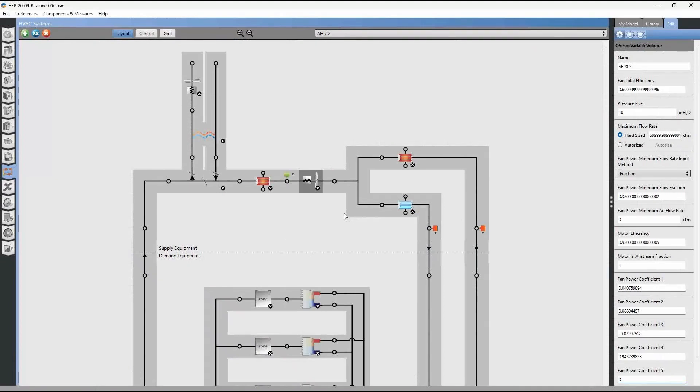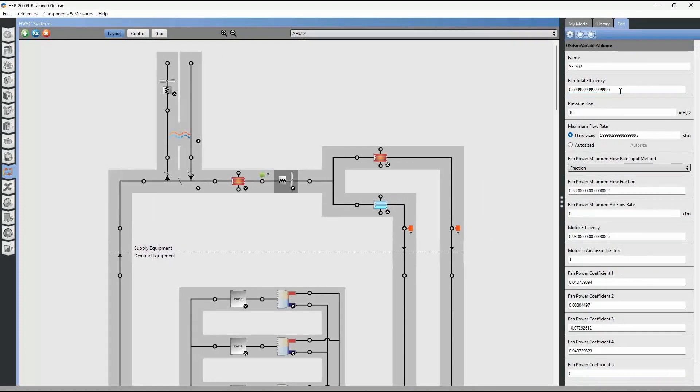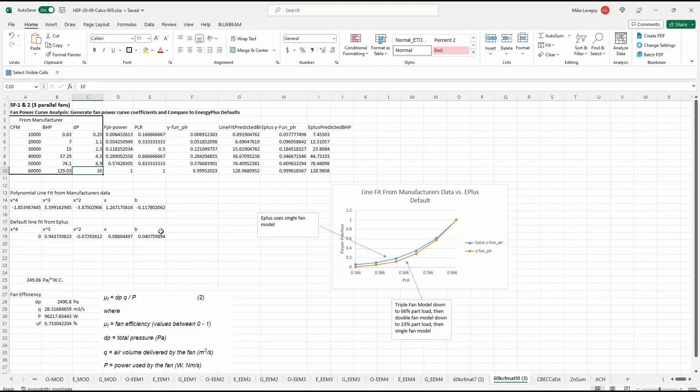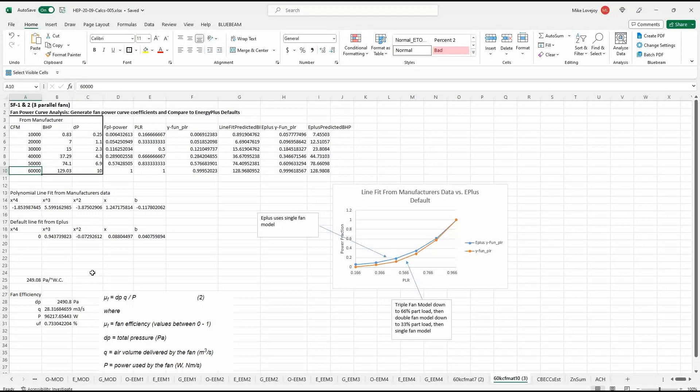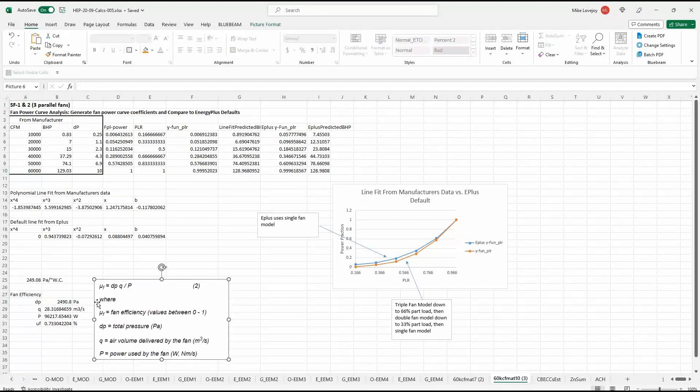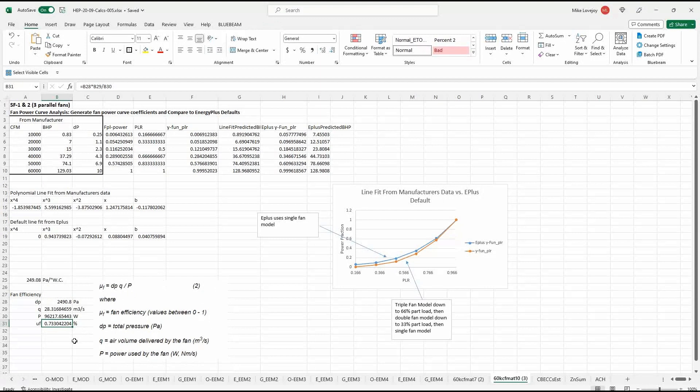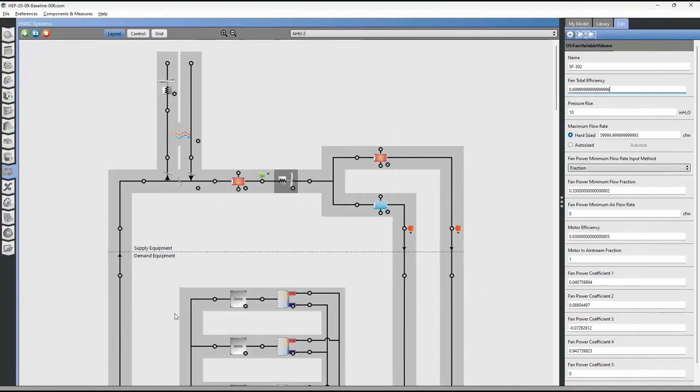And then what we can do is we can go to OpenStudio and select the fan. And the first input value that we need to input is the fan total efficiency. So we're starting out with a fan total efficiency of 0.7. And this is the default EnergyPlus fan efficiency value. And we need to calculate the new efficiency value. And this is at the design flow rate. So our design flow rate is at 60,000 cubic feet per minute. And you can just calculate fan efficiency with a simple efficiency equation. And we come up with a fan efficiency of 73.3% at full flow.